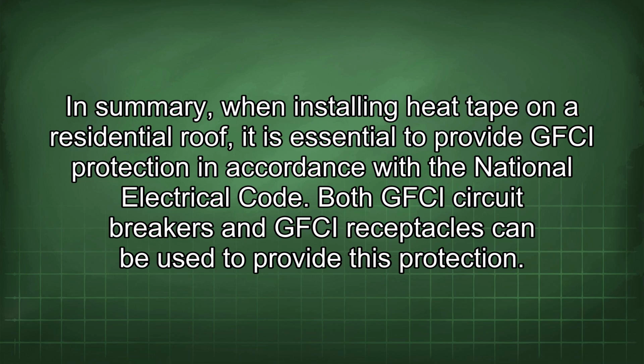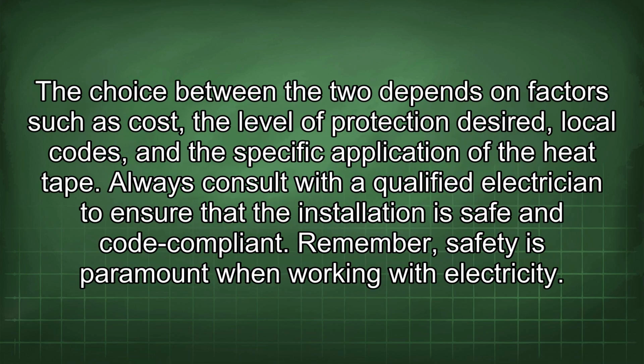accordance with the National Electrical Code. Both GFCI circuit breakers and GFCI receptacles can be used to provide this protection. The choice between the two depends on factors such as cost, the level of protection desired, local codes, and the specific application of the heat tape. Always consult with a qualified electrician to ensure that the installation is safe and code compliant.